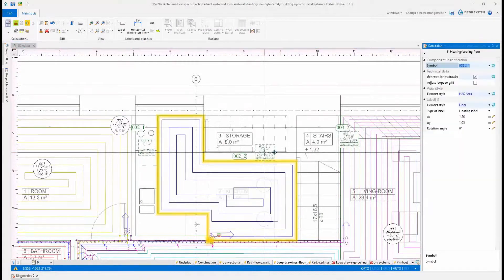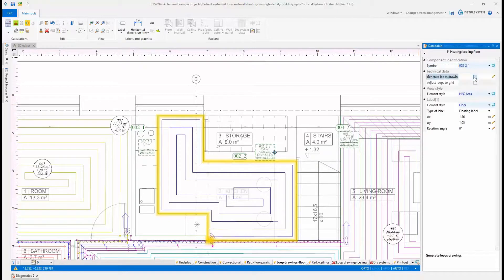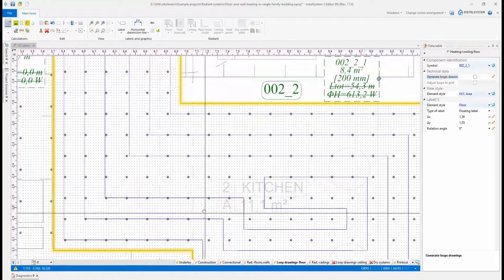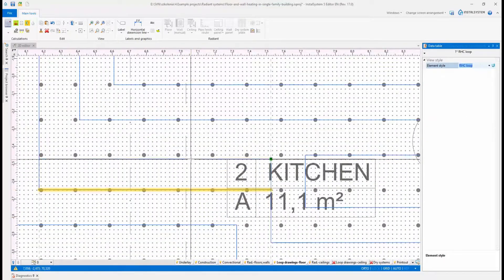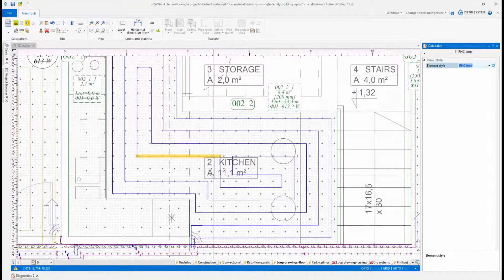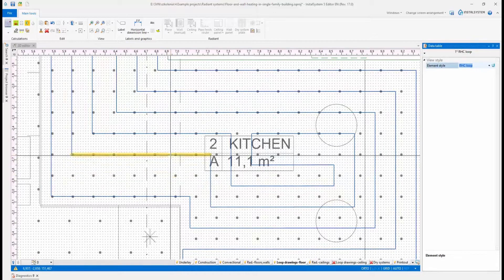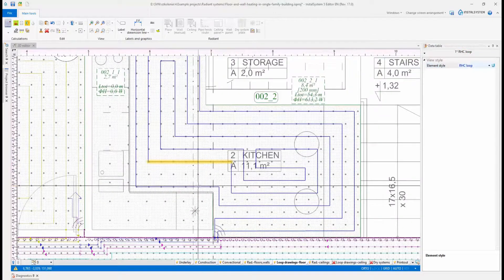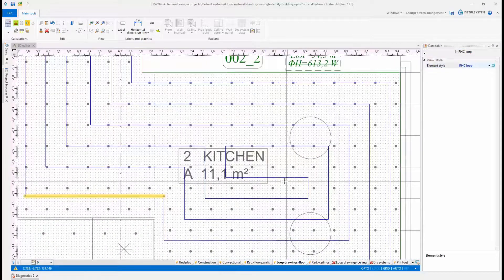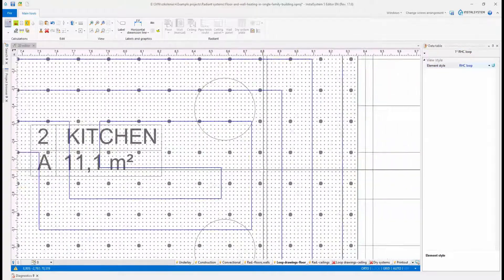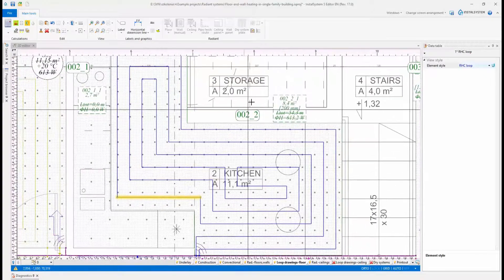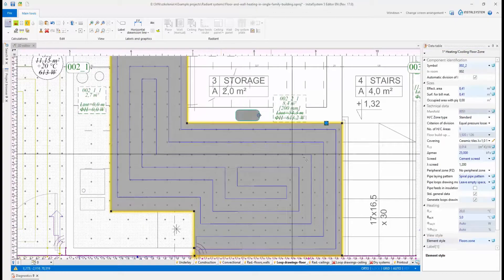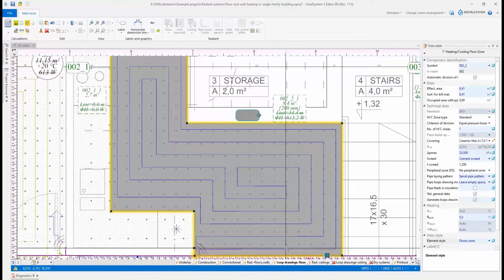In case of need for correction of automatically generated loop drawings, the drawing grid and auto mode are useful. Grid evenly covers the entire heating and cooling zone. The distance between big grid points is consistent with the distance calculated by the program for the zone, which makes it easier to keep a constant distance for the loop being laid. Depending on the zoom level of the view, when you draw or move loop segments, the auto mode snaps segments to big or small grid points. In addition, it is possible to align the drawing grid to any edge of the zone.